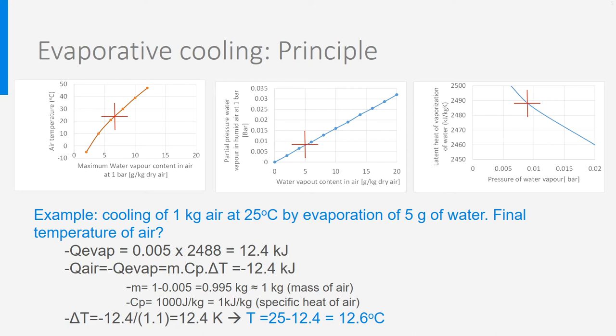This heat is taken from the air, which will then cool down using the well-known formula Q is MCP delta T. M is 1 kg, or to be precise 0.995, but we round it to 1. Cp of air is 1 kJ per kg Kelvin, so delta T must be 12.4 divided by 1 times 1, which is 12.4 degrees. So, the final temperature of the air will be 25 minus 12.4, which is 12.6 degrees Celsius. This gives a huge potential for cooling and costs no energy.